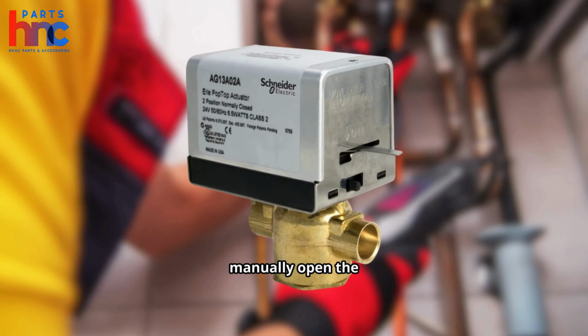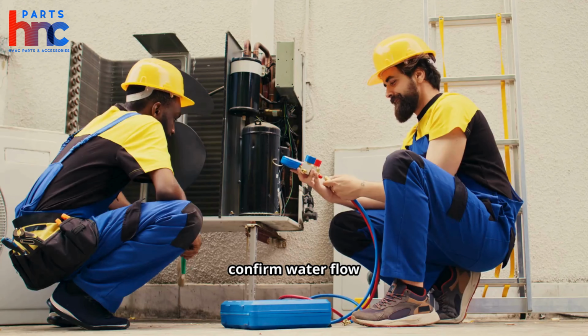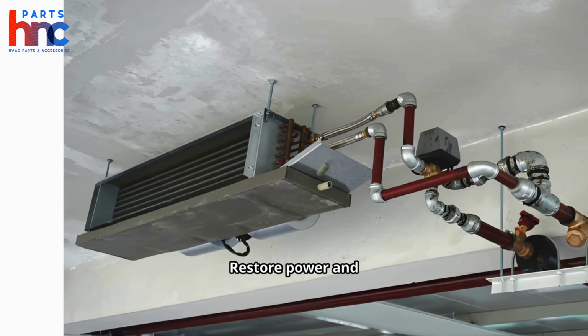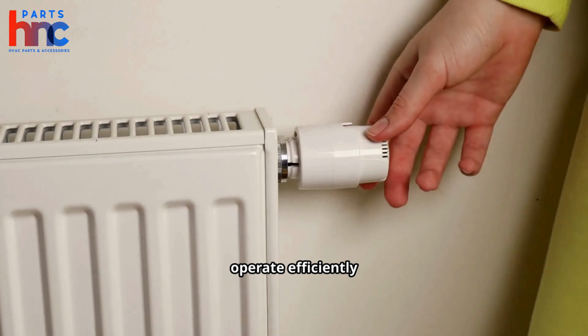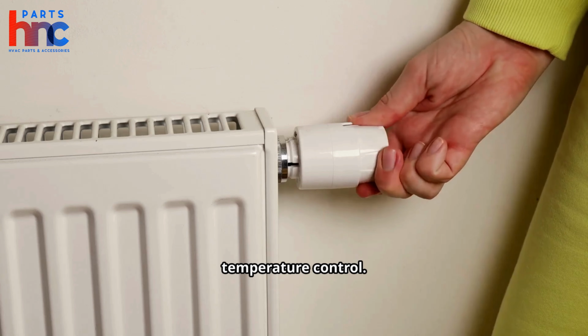Reinstall the actuator and manually open the valve by pressing its spring to confirm water flow and check for leaks. Restore power and run the FCU. It should now operate efficiently with balanced temperature control.